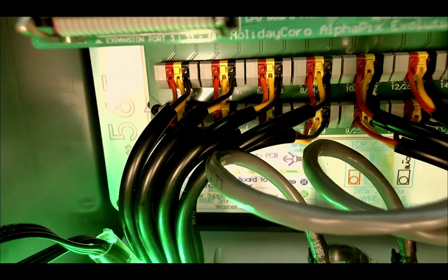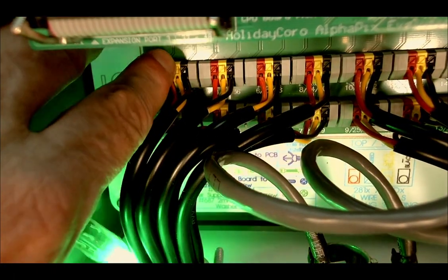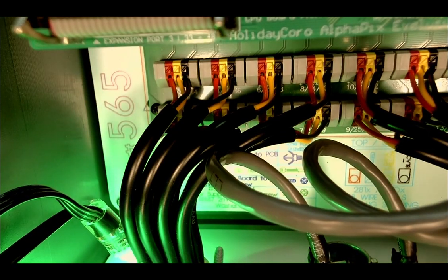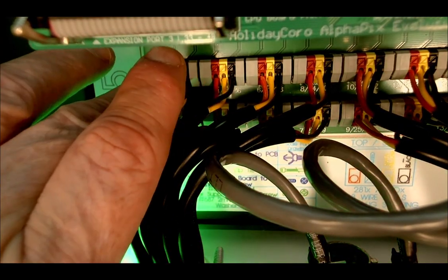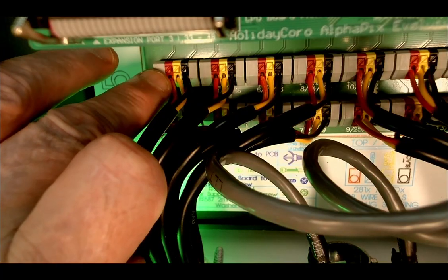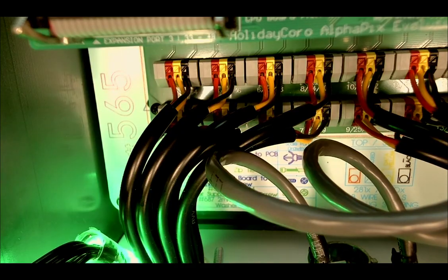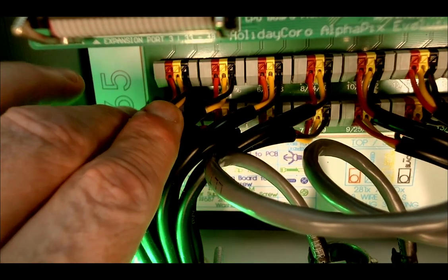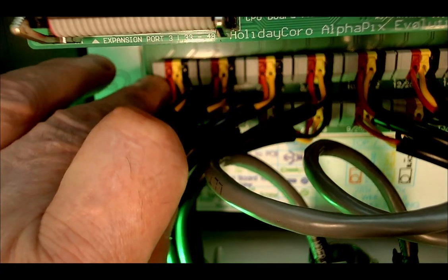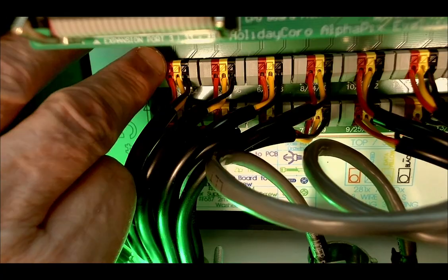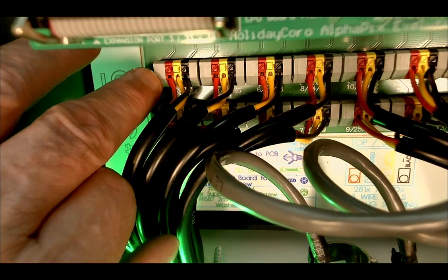Down here at the bottom, depending upon the configuration of your particular controller, you will see that there are connections here. And these are push to connect connections. Yours may have screw type terminals, so they may have come loose. This is the most modern version, and these generally cannot come loose if factory installed. But if you've built this yourself, maybe you have a wrong or loose connector. Also, our controllers generally always have a color coding system, and you can see that the wires are red, yellow, and black, and they're all in the right spot.